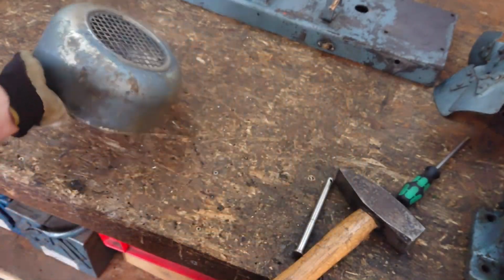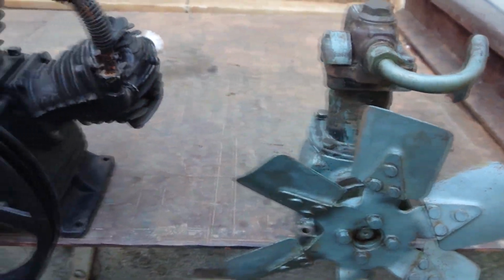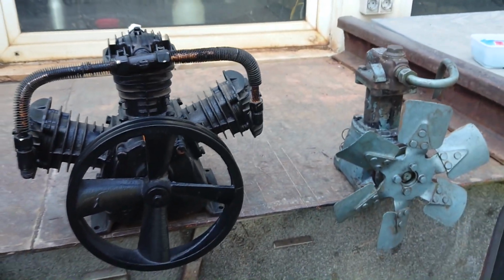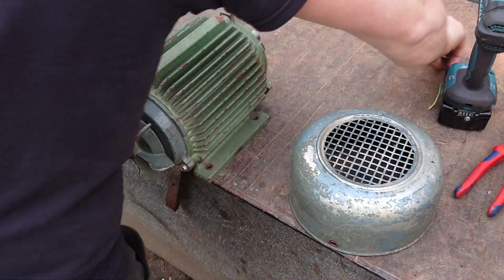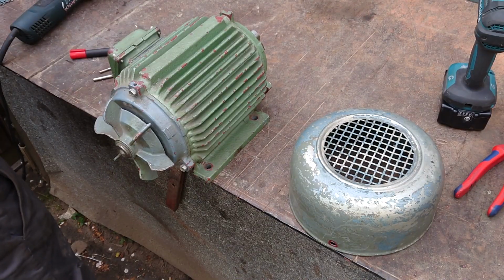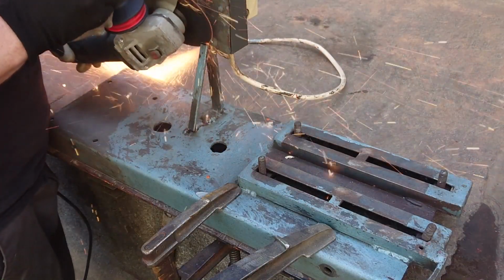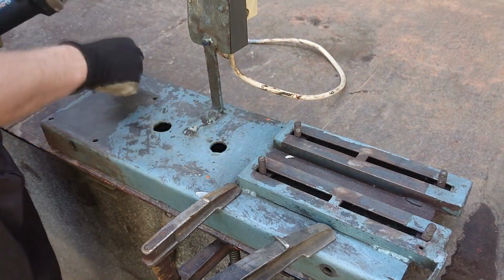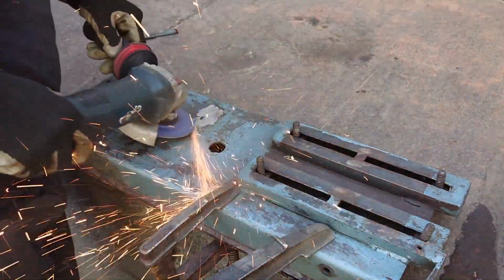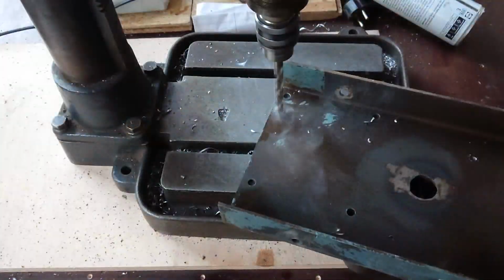But since we are not going to reuse these old components, but rather install a new, bigger pump and a more powerful motor, the equipment deck needs to be modified to some degree. The steel parts holding the old motor protection switch are cut off and the welds are ground down. A new set of holes was also drilled to hold the bigger pump in place.